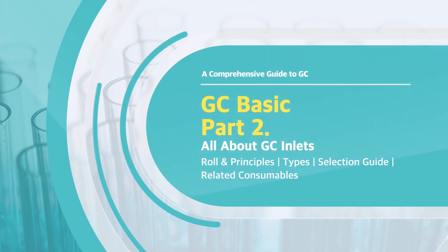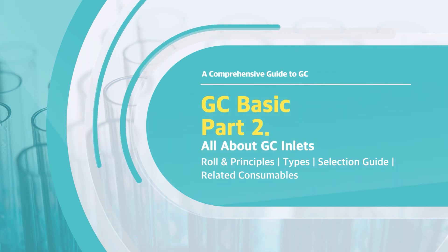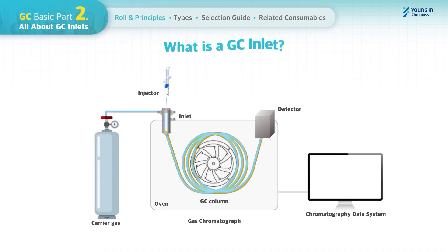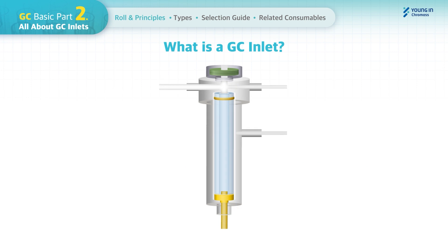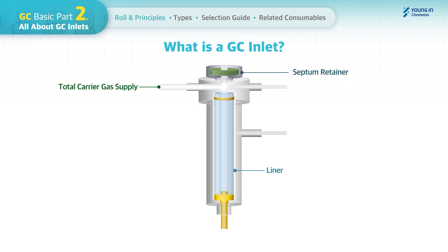What is a GC inlet? The main role of the GC inlet is to deliver an accurate and reproducible sample introduction into an analytical column. A GC inlet is commonly configured with a septum retainer, an injection port, a total carrier gas supply line, and a liner where the liquid samples get vaporized, along with a septum purge line and split vent line.